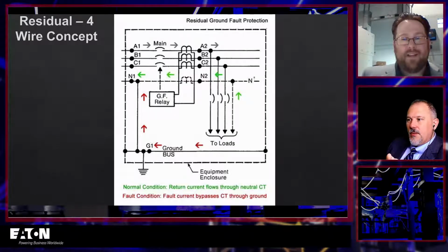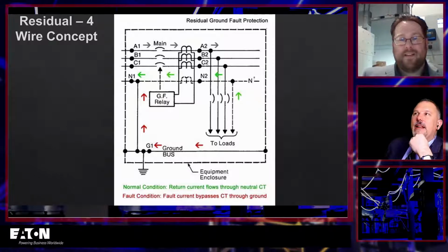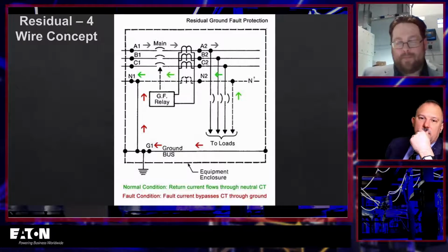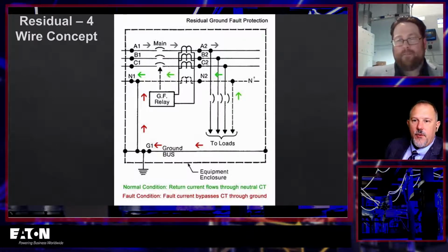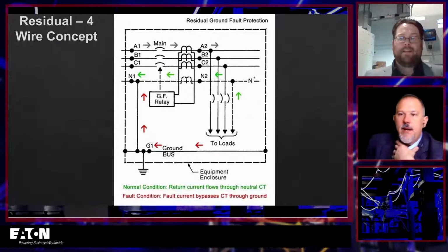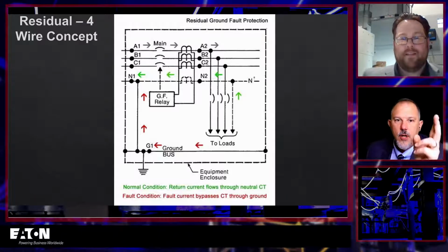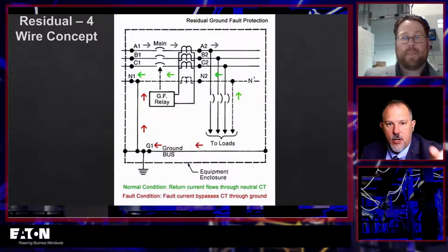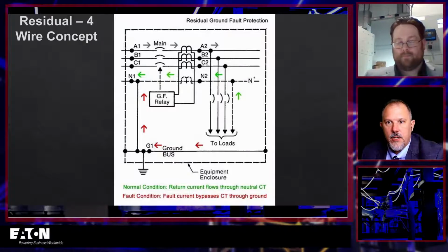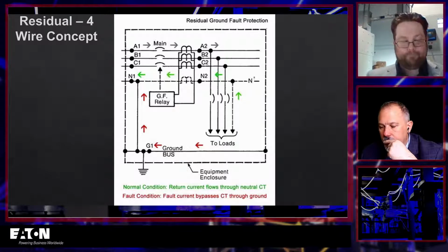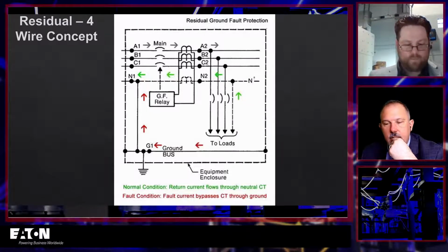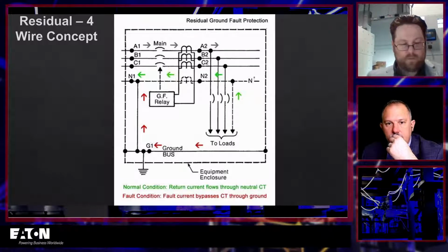here, you're doing the typically though. I mean, I'm trying to think if we do that in our breakers. We probably wouldn't. Maybe in some breakers we do a residual, because you'd have to have the neutral. So if you have a 4-pole breaker, I could do the residual in my breaker if I have a CT around the neutral and the 3 hots, internally to the brain of the electronic trip unit. I could do my calculation from a ground fault perspective.